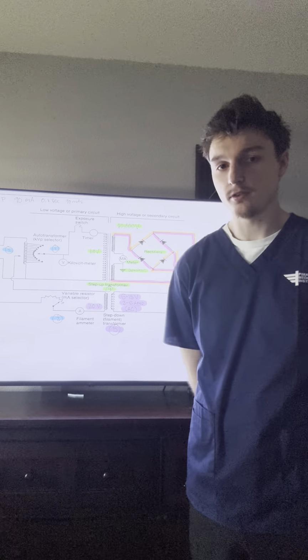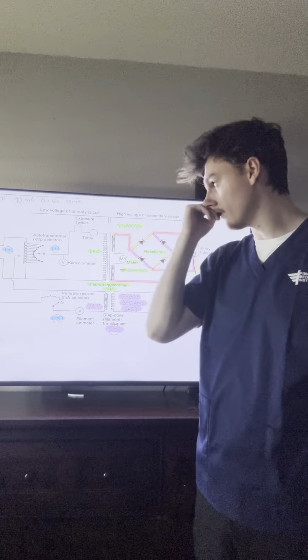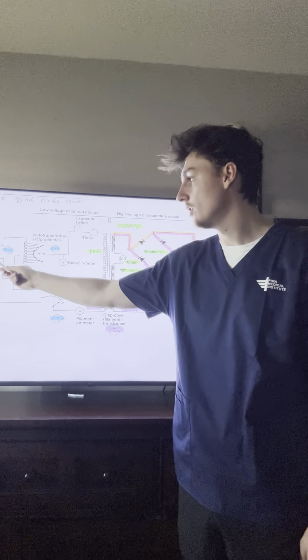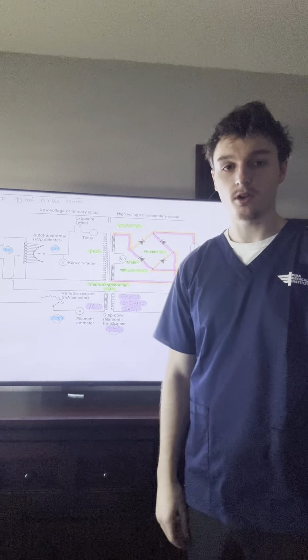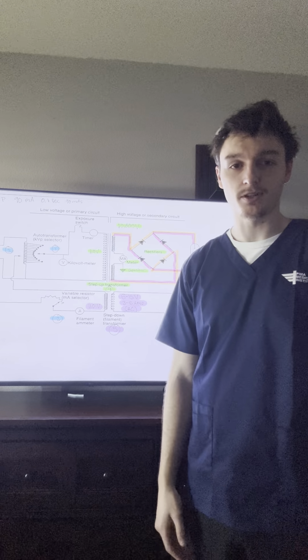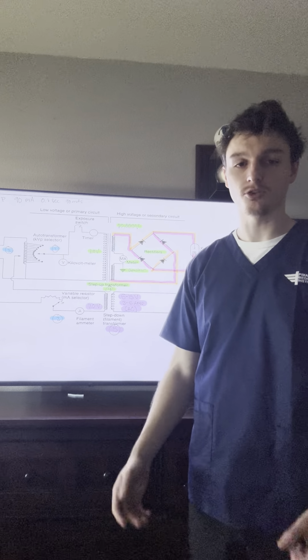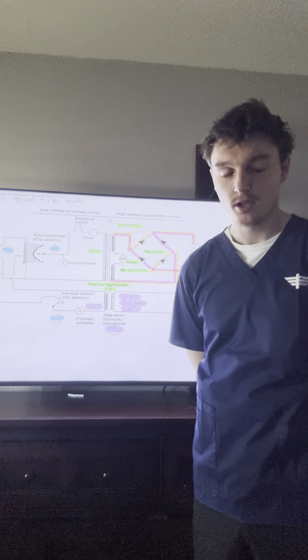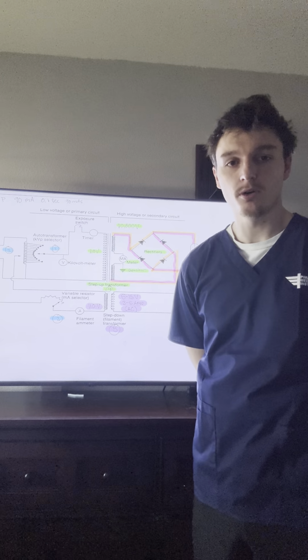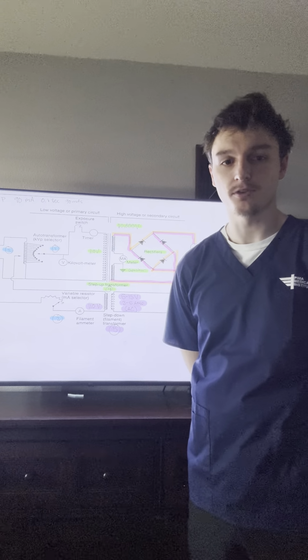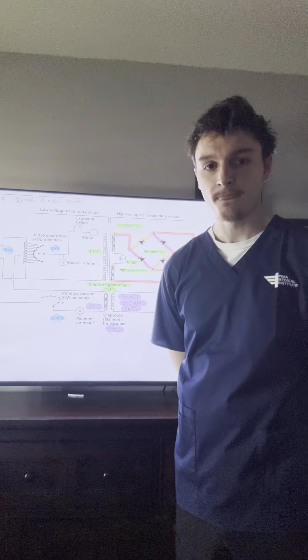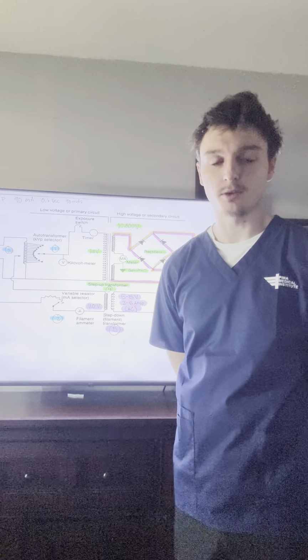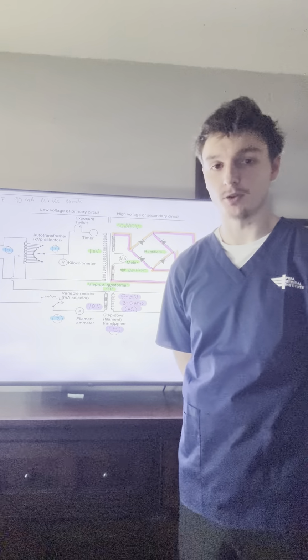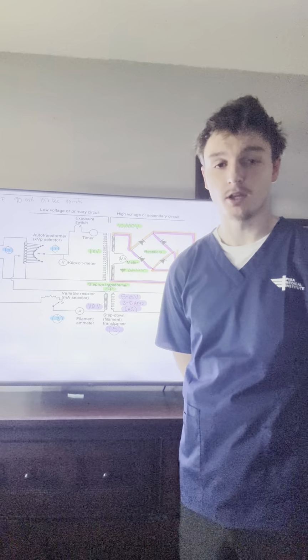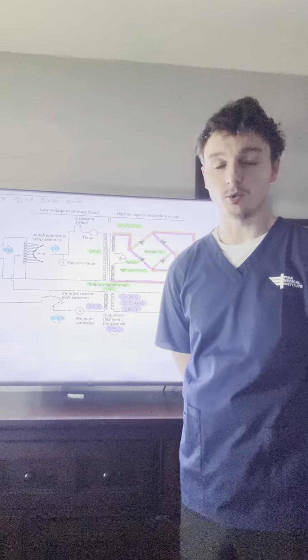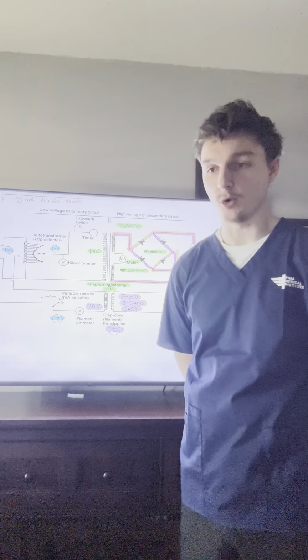Now, the first thing that we're going to have to talk about is our main switch. We're going to turn that main switch on, which is important because we have to warm up the machine. It'll trigger the warm up procedure, and the warm up procedure is important because it'll warm up the specific parts in the machine that need to be warmed up, like our filament and our anode. We need those to be working at peak performance.